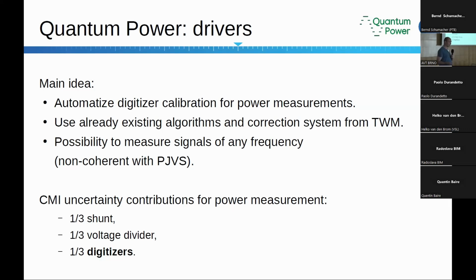For example, if we got a source of 53 Hertz, and I can generate on the Josephson only 60 Hertz, I can say, for example, that this digitizer is quite good and the gain doesn't change much with frequency. So I calibrate the digitizer on the frequency of 60 Hertz and use it to measure the source of 53 Hertz.